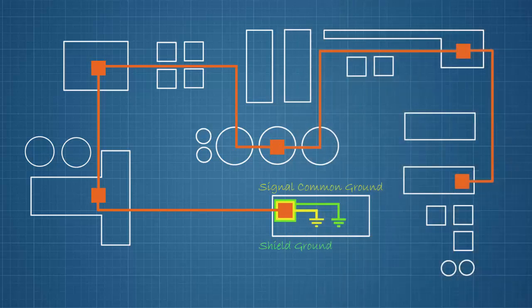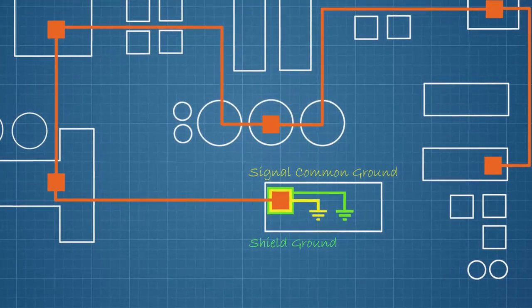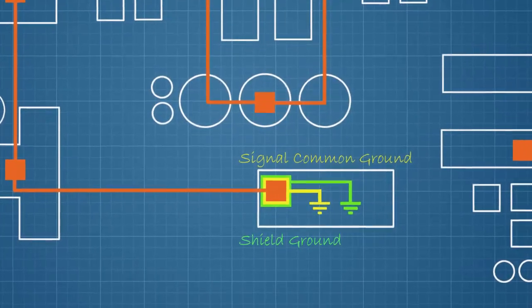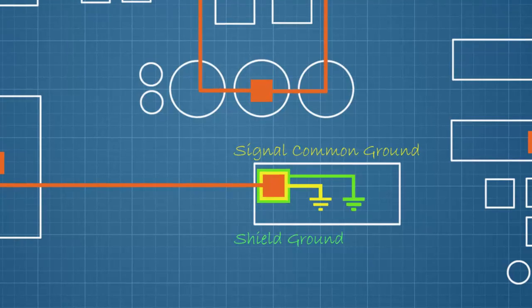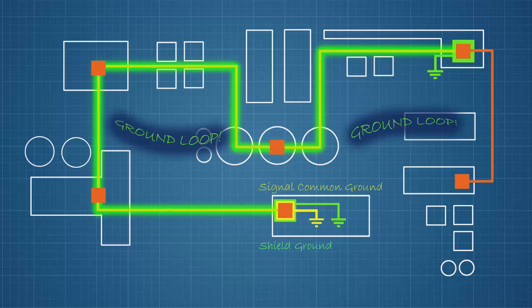When wiring up your network, use the common signal reference cable to tie the ground potential of each port to the same ground. You should also ground the shield at only one point in the network. If the shield is grounded at several points, you may get ground loops, current flowing through the shield, and this will induce noise on your signal wires.